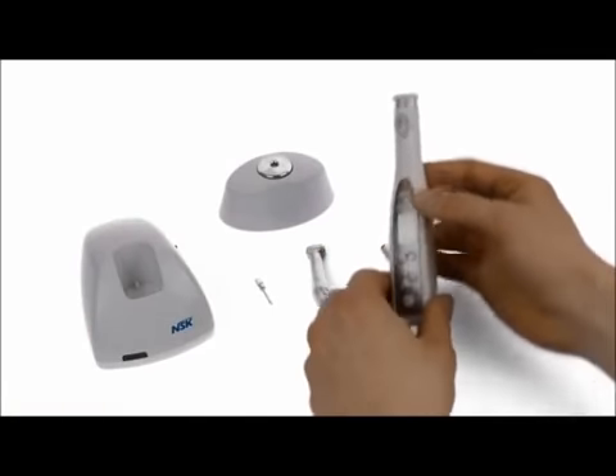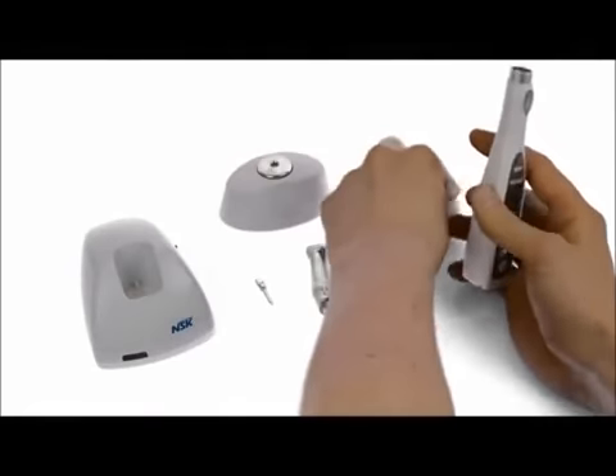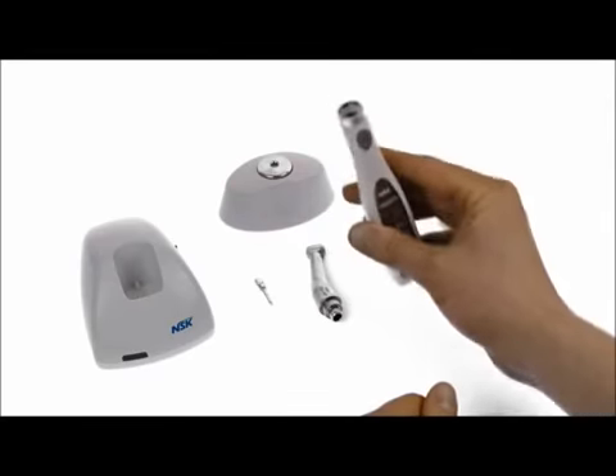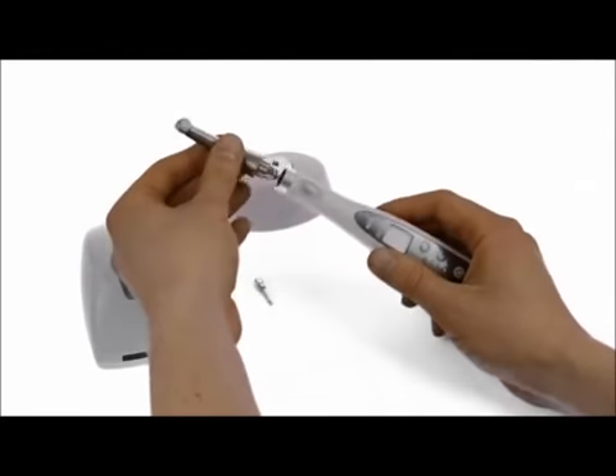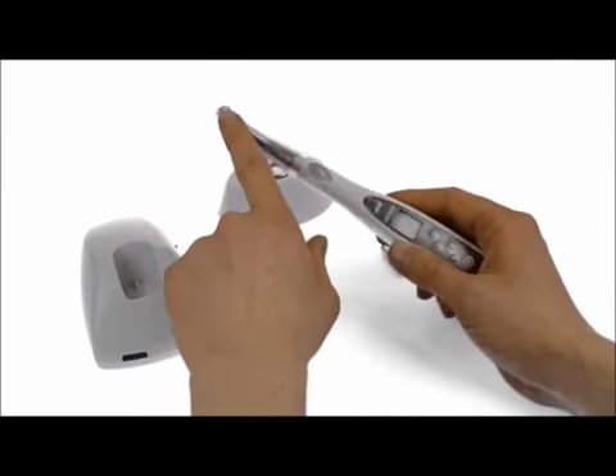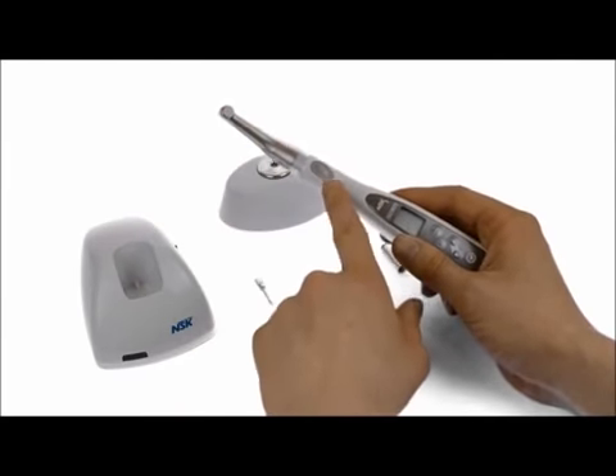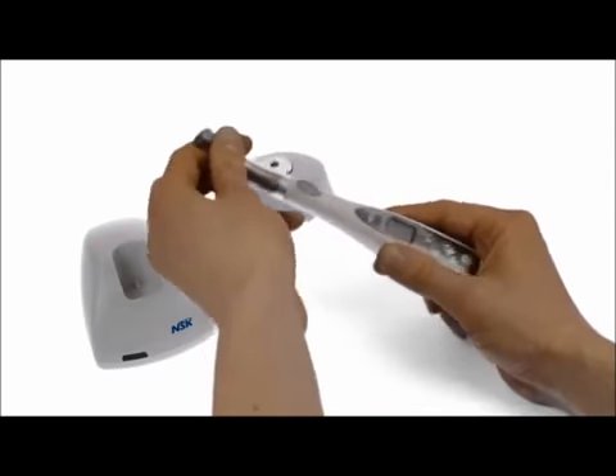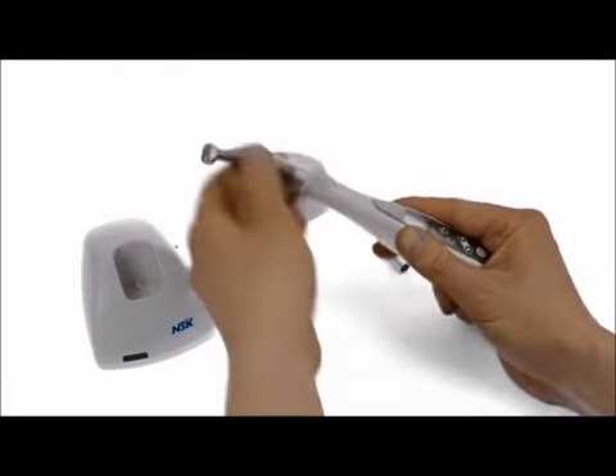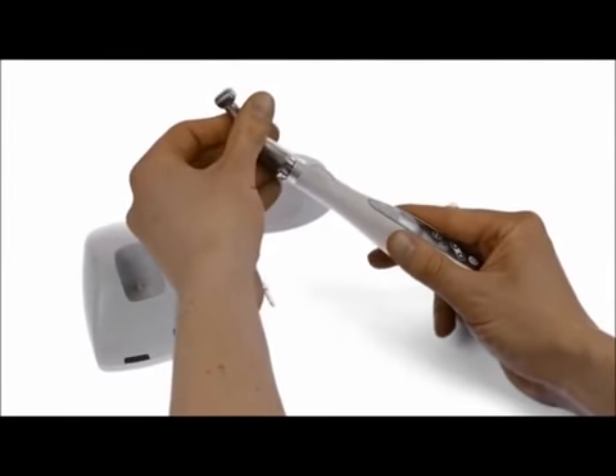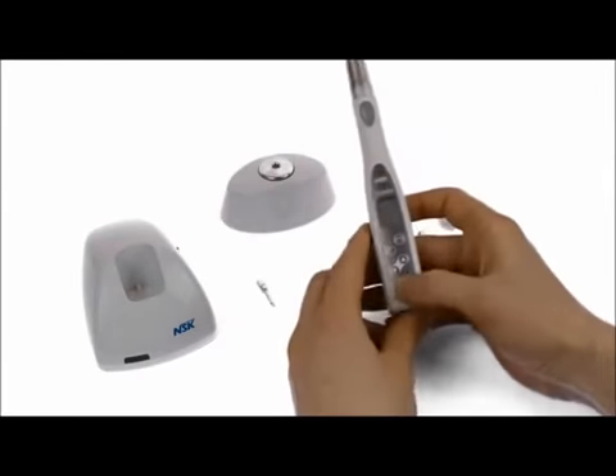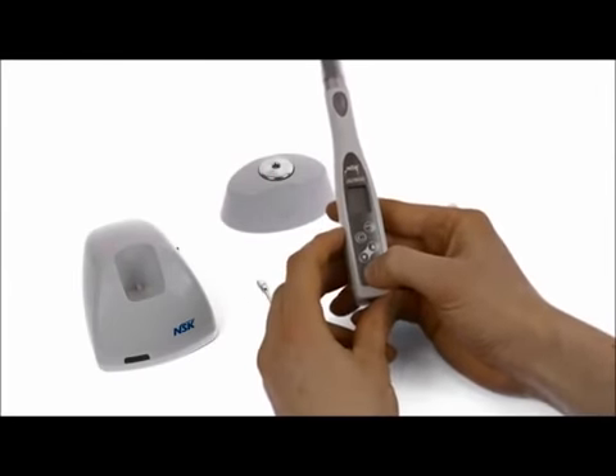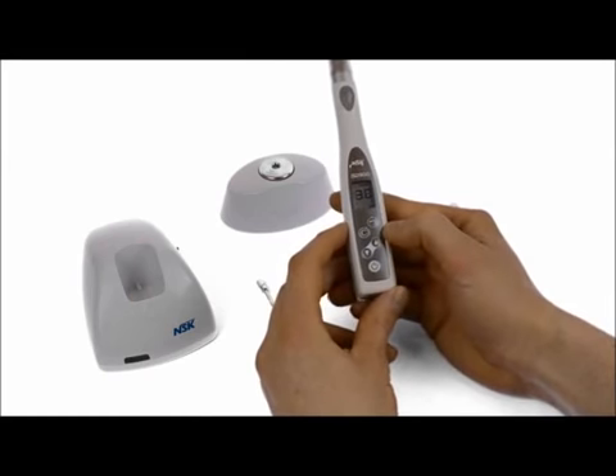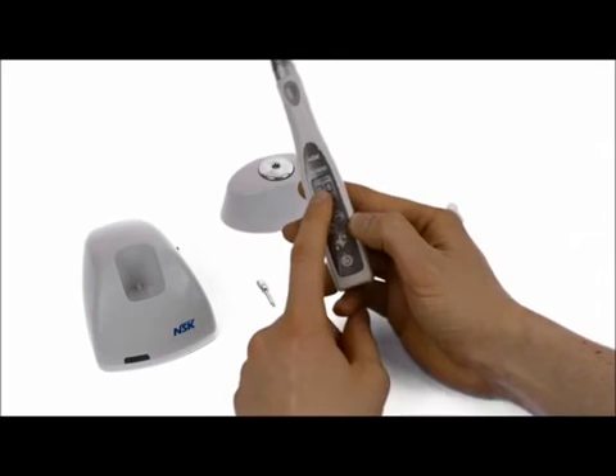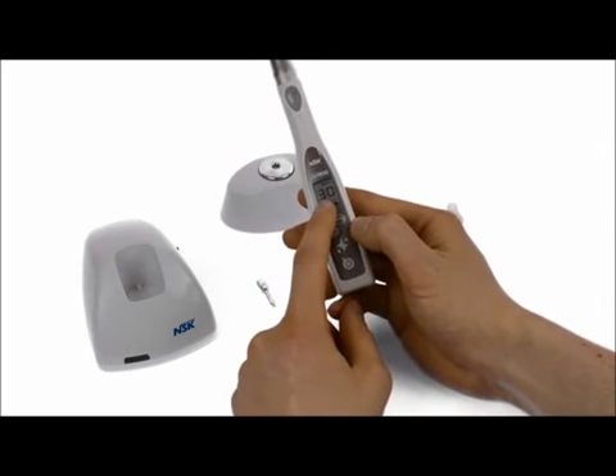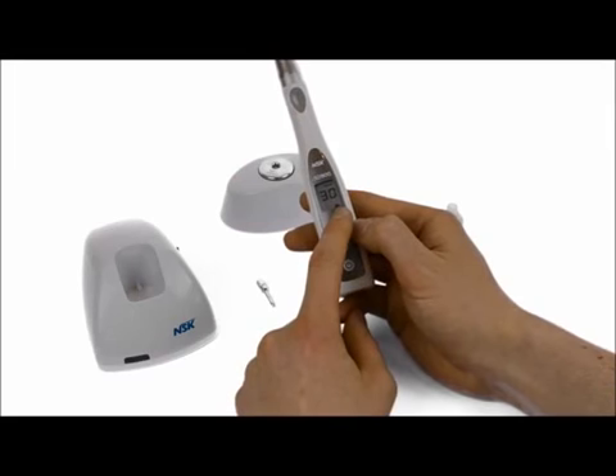When you're ready to use the unit, we take the dust cap off the head, which protects all the electronics inside, and then connect the handpiece. Now, I like to line up the burr button and the activation button on the motor for ease of use, but you can put this in any orientation on the unit depending on your access to the patient's mouth. So then start, obviously, by turning the unit on, pressing the power button, and then it will beep. Now on the display you can see the revolutions per minute of the burr in the handpiece, the torque value, and the level of battery life that you have.